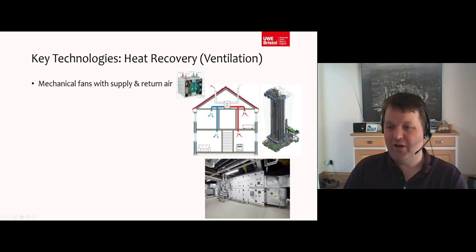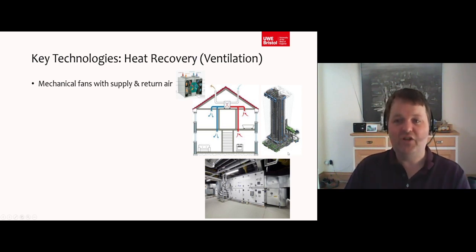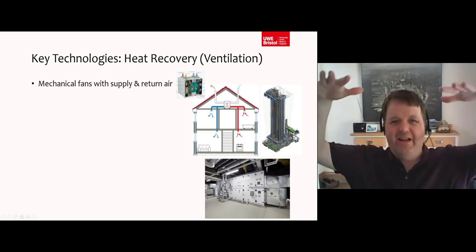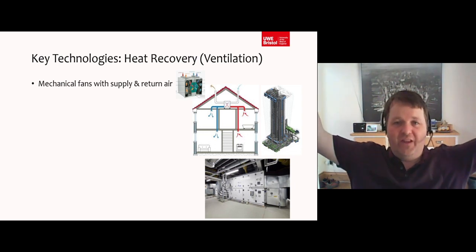This is the Walkie-Talkie building in London, stripped of everything except its mechanical ventilation systems. But it's the same thing up here. You have big pieces of kit, which are multiple numbers of this. They're taking air from outside, they're filtering it. You get injection of heating and cooling in here in these ones, which is the reason why it's not passive house. And then you get that fresh air, conditioned air being pumped down into every floor and supplied into every floor. Normally in a grill spread out around the room so that you don't get chills.